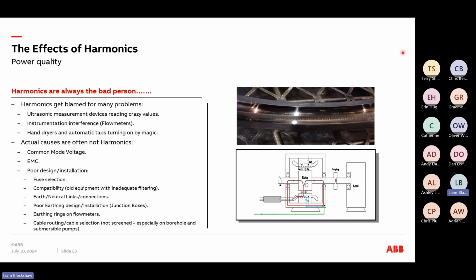Things like your connections, your earth neutral link connections: have they been terminated properly? Is it a poor earthing design or installation? And things like earthing rings on flow meters, for example. But also the key thing is, how is that cable being routed? What type of cable has been selected? Is it a screened cable or is it not screened? Which is very apparent, especially on boreholes with submersible pumps, where ideally you need to have a screened cable, and in some cases when they become predefined, they may not have that screened cable, at least anyway.